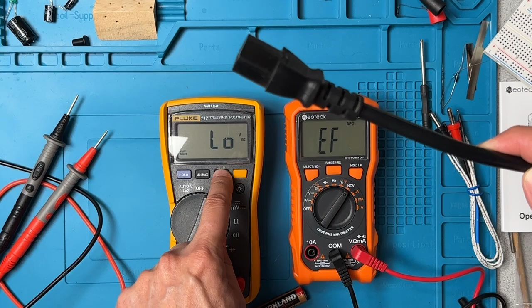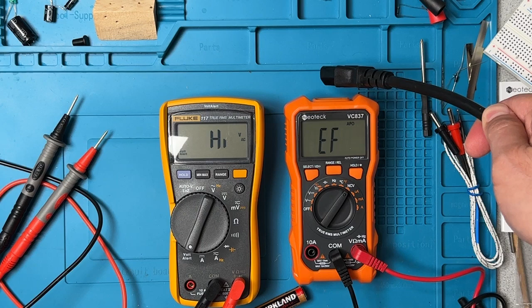With the Fluke, it's very similar on low, but with the Fluke I have the option of high sensitivity, and in that case the Fluke is able to sense the cord way out here, whereas with the Neoteck, nothing happens. So if you're in an area and concerned, that sensitivity can be important, because you could have a lot of wires around and you'd like something sensitive. So I think you can see that when it comes to non-contact sensing, the Fluke is much more capable than the Neoteck.